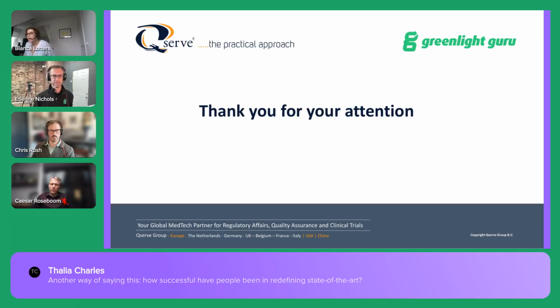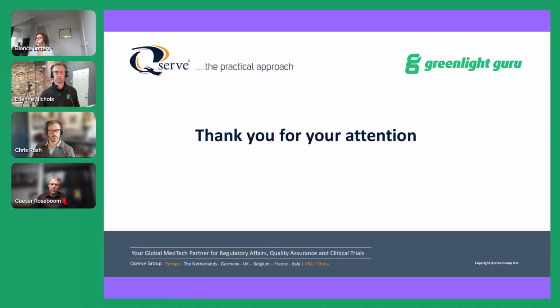Yes. If you look at novel devices, the first question I would ask myself is, why is the device novel? Because if the device is novel in materials, there may be very similar devices on the market that do the same. Then you can use the normal way of looking at state of the art. One of the new devices where recently the first version was approved is a tricuspid heart valve.